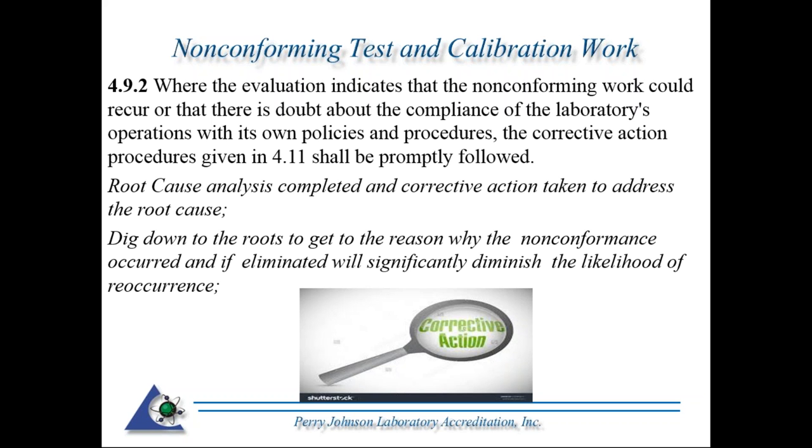had to take a short-term action, remove a piece of equipment out of service, or do some retraining, whatever it happens to be, if it's indicated that this could possibly repeat itself, or that the organization has determined that they are not complying with their own policies and procedures, then corrective action needs to be followed. In other words, in 4.11, a root cause analysis would need to be completed and corrective action taken to get at the root of the issue, to dig down to the reason why the nonconformance occurred, and if eliminated, will significantly diminish the likelihood of reoccurrence.